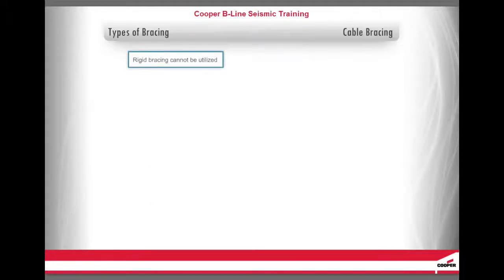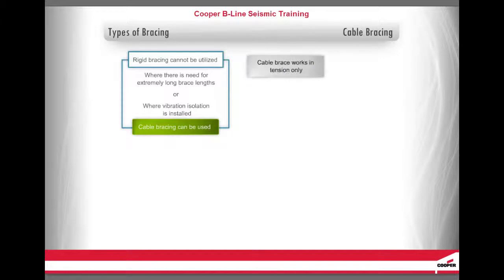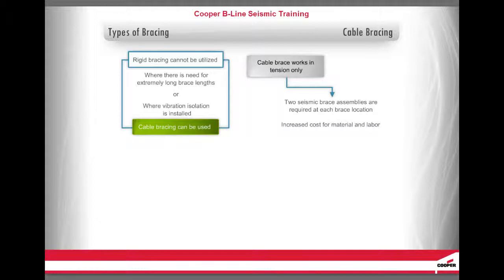In instances where rigid bracing cannot be utilized — such as the need for longer brace lengths or where vibration isolation is installed — cable bracing can be used as an alternative option. For a cable brace, since it works in tension only, two seismic brace assemblies are required at each brace location. In comparison to rigid bracing, there is an increased cost for both material and labor, but in some cases it is the only choice available.